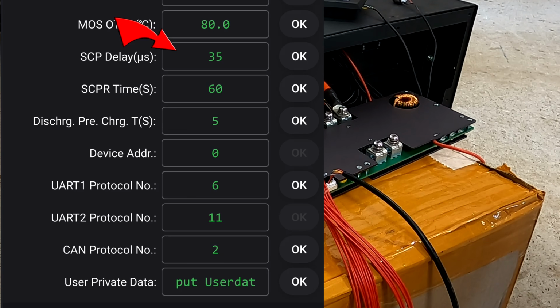We then have a setting here for the short current protection delay. It sits at 35 microseconds. You want to react fast, and here again it waits for 60 seconds and checks again if the short current is still there. And then we have a discharge pre-charge current. I think this is for when you connect larger inverters to the BMS, which have capacitors that need to charge up. But I'm not sure how this 5-second rule comes into play with the short current protection of the BMS, because connecting capacitive loads is like a short current for the BMS. So I have to ask how this functionality actually works here.